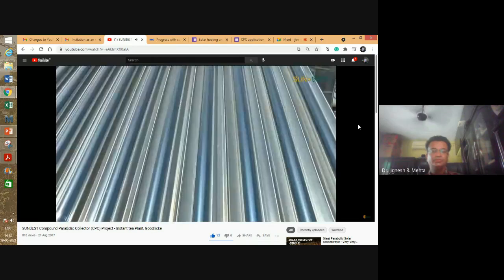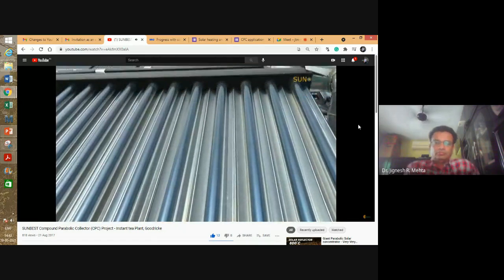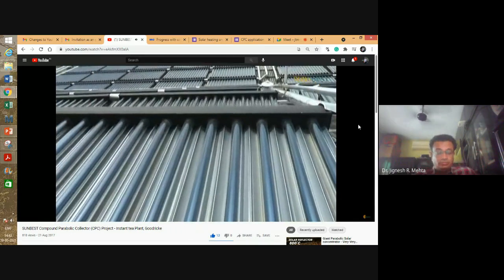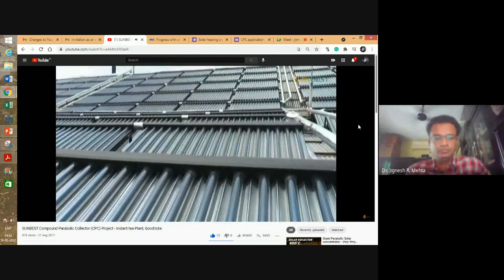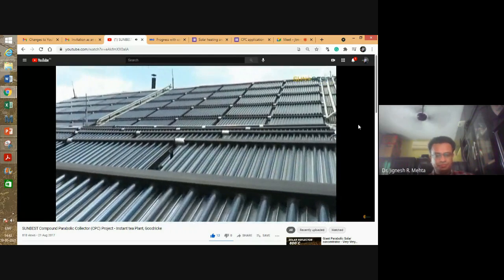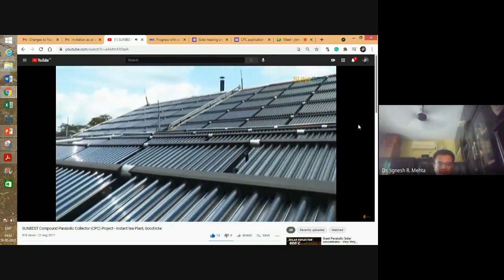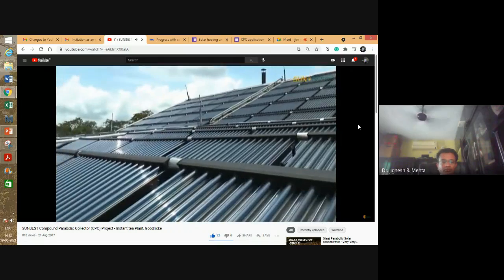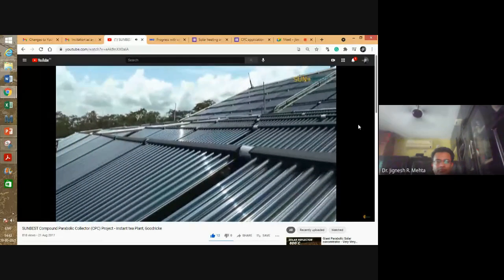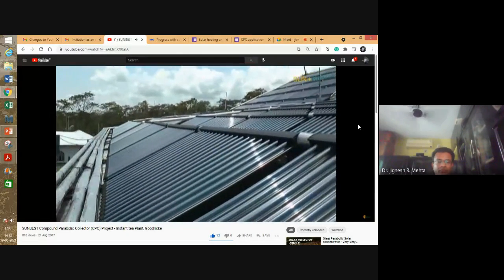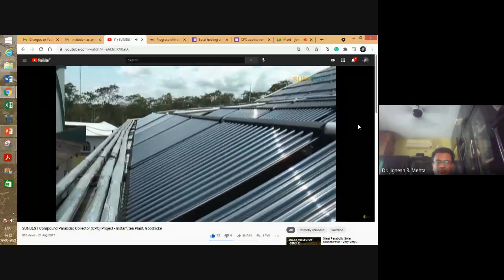To extract maximum benefit out of the solar collectors, two actuator valves were installed, which is basically a PID controller. It senses the input water temperature and releases only that much amount of steam which is required to increase the temperature to 80 degrees centigrade, especially during not so sunny days or cloudy days.